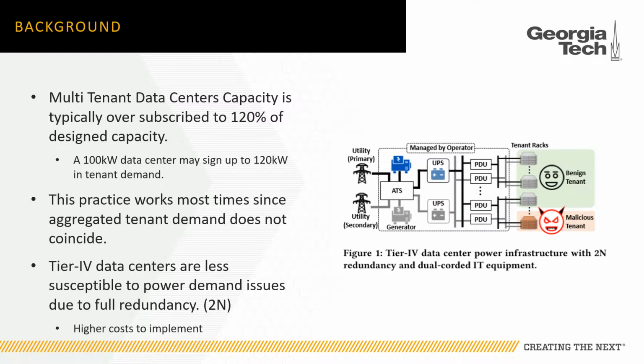Now, moving on to some background, multi-tenant data center capacity is typically oversubscribed to 120% of the design capacity.